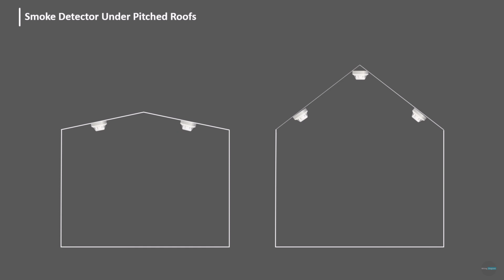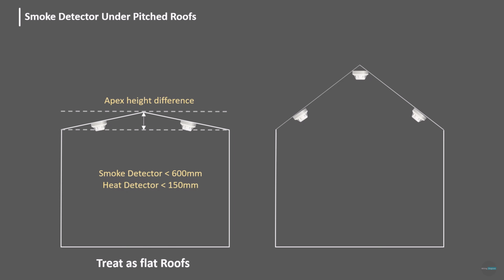So far, we've learned how detectors are designed under flat horizontal ceilings. Now we'll see how to design and space detectors under apex or pitched roofs. In apex roofs, the apex height and roof angle play a key role in detector spacing. If the apex height is less than 600 millimeters for smoke detectors, less than 150 millimeters for heat detectors, then the roof is treated as a flat horizontal ceiling, and the standard flat ceiling spacing rules apply.